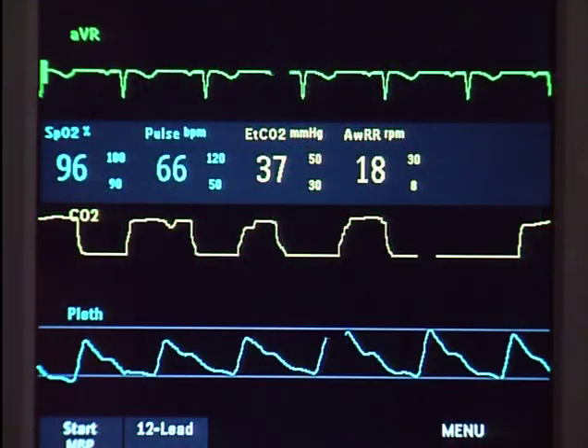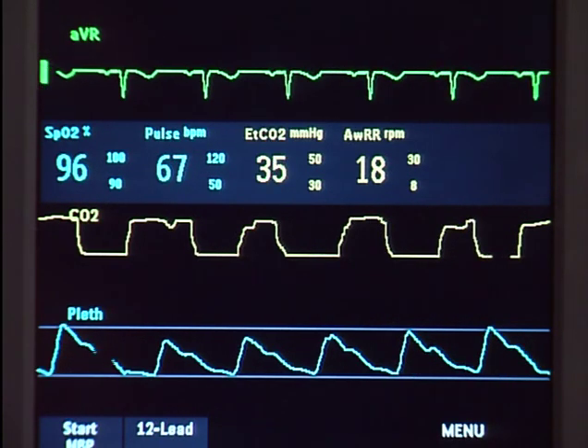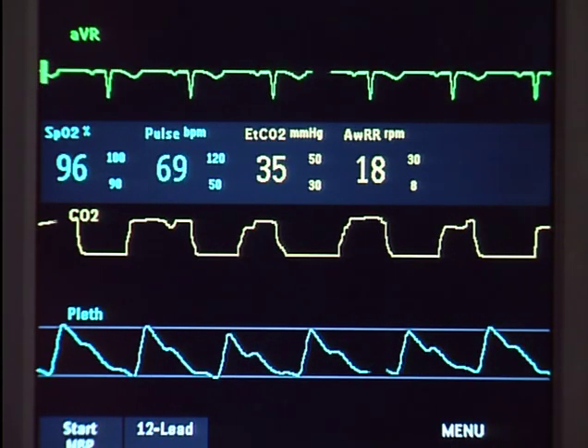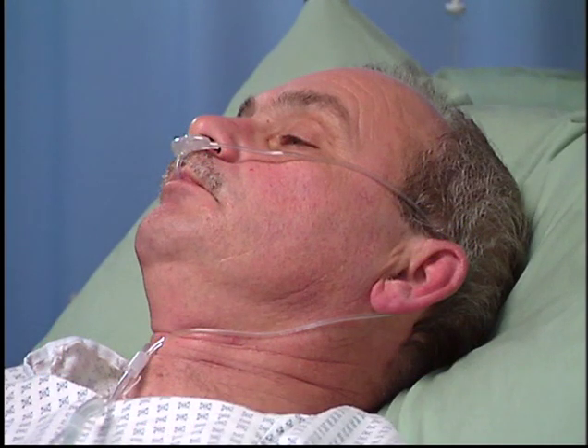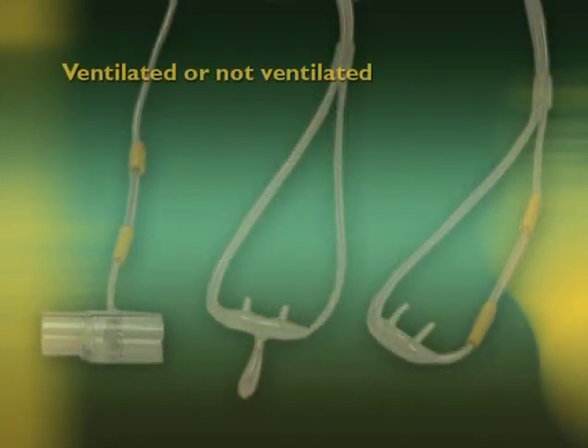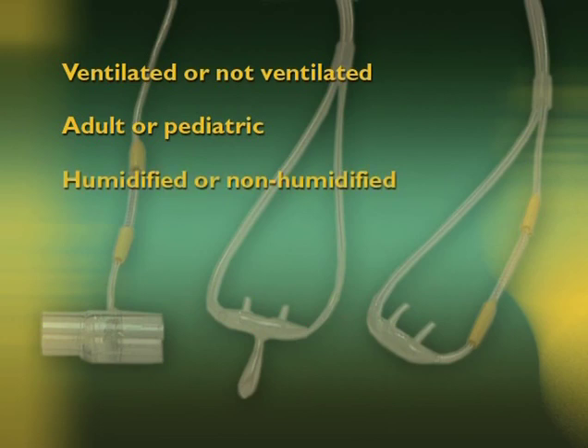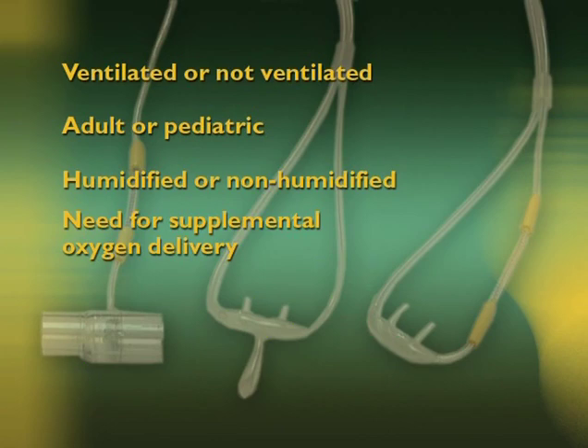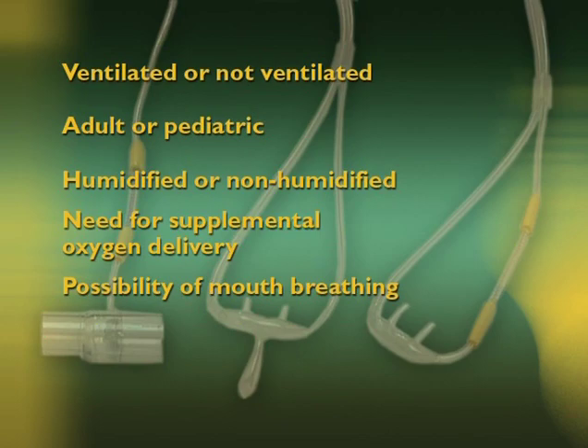The MRX can also measure carbon dioxide or CO2. Philips uses the microstream method of sidestream CO2 measurement. The first step in setting up the microstream system is to select the appropriate filter line. There are 5 factors to consider when selecting the filter line. Patient situation: ventilated or not ventilated. Patient type: adult or pediatric. Ventilation type: humidified or non-humidified. The need for supplemental oxygen delivery, and the likelihood that the patient will switch between oral and nasal breathing.